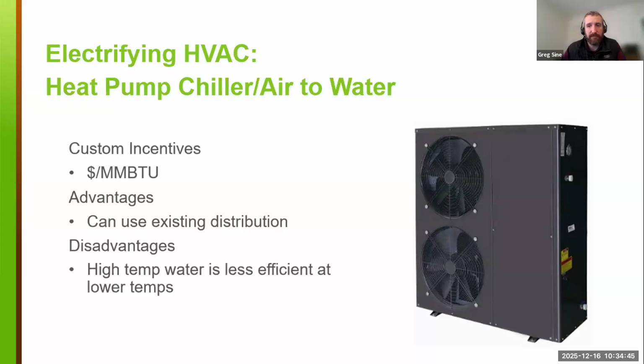It's worth noting that Kevin had touched on low temperature conversion earlier. The equipment that's available on the market now generally has a lower temperature output capacity than that of a boiler, and the higher the temperature output, the COP or the efficiency can suffer a bit. So there's a balance point where it makes sense to run your air to water heat pump and perhaps use an existing boiler for backup at colder ambient temps. There are no prescriptive rebates available for this type of equipment, given how variable the application of it would be. We could look at it on a custom basis.